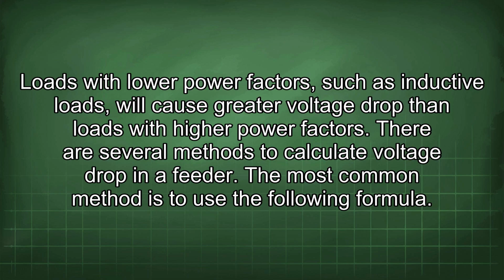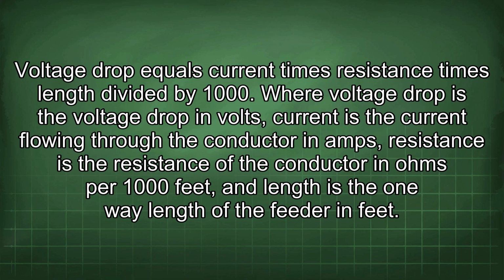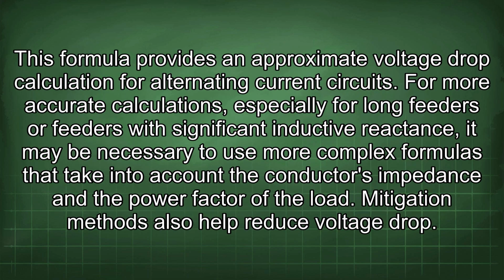There are several methods to calculate voltage drop in a feeder. The most common method is to use the following formula. Voltage drop equals current times resistance times length divided by 1000, where voltage drop is the voltage drop in volts, current is the current flowing through the conductor in amps, resistance is the resistance of the conductor in ohms per 1000 feet, and length is the one-way length of the feeder in feet. This formula provides an approximate voltage drop calculation for alternating current circuits.